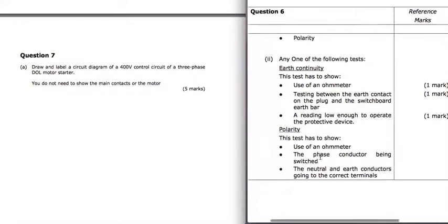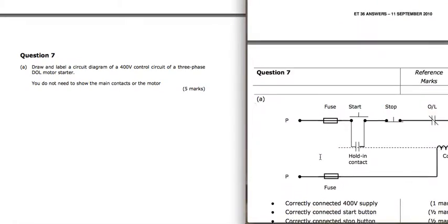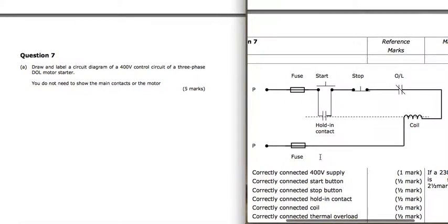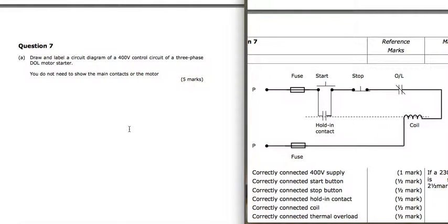Question 7, we're looking at a DOL starter. Now, I must admit I've never seen the DOL drawn like that, because they're asking for it to be drawn without the main contacts or the motor. So you're just looking at the control circuit. So the phase to a start switch, stop switch, overload, coil and fuse in both parts there, and we've got a hold-in contact that's operated from that coil in parallel with the start.